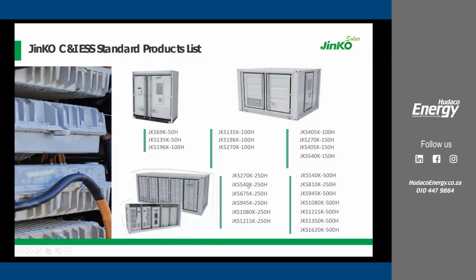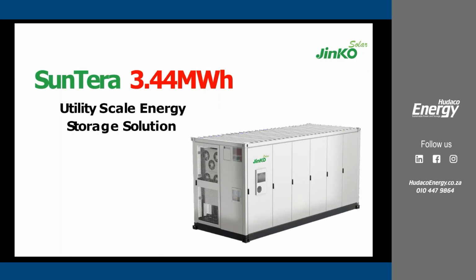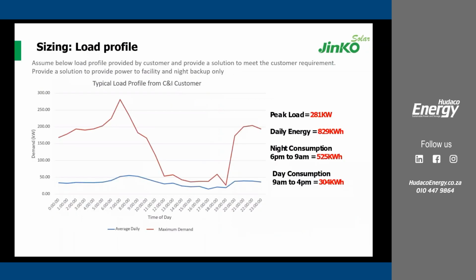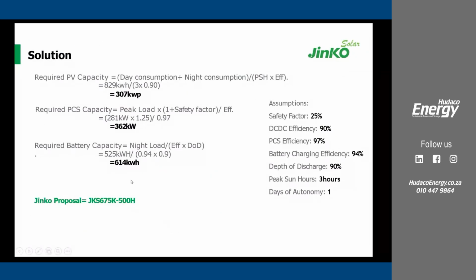So 540 is less than 614, so the system will be undersized. Of course it's preferable that we choose the next level available close to 614, that is 675 kilowatt hours. Then for the PCS side, our requirement is 362 kilowatts. We don't have a 362 kilowatt unit, so we can choose the next level, the 500 kilowatt PCS.